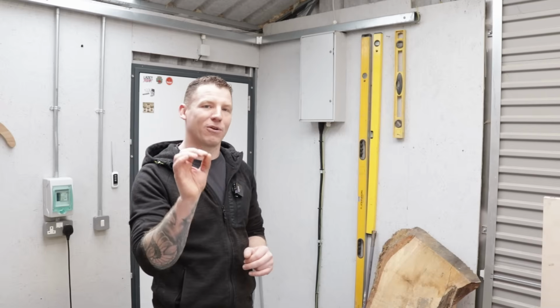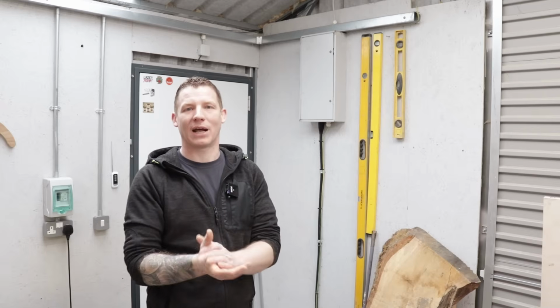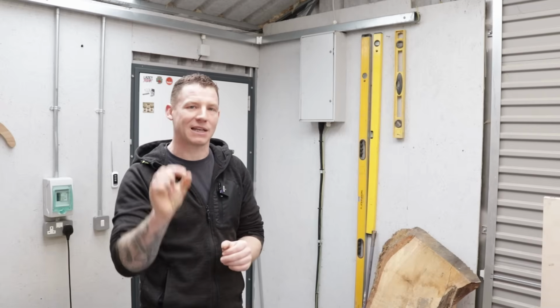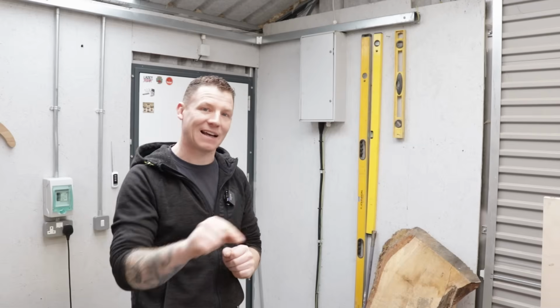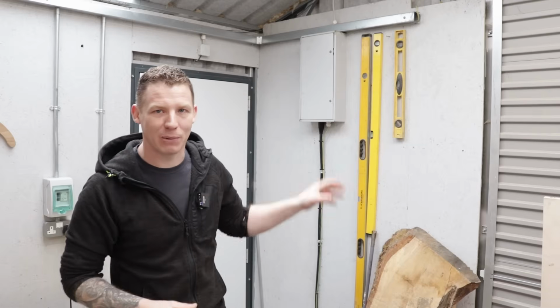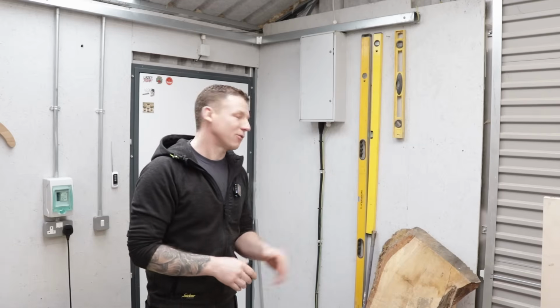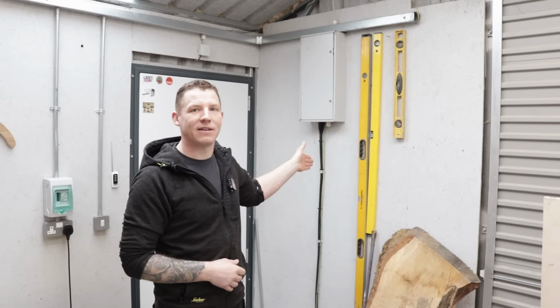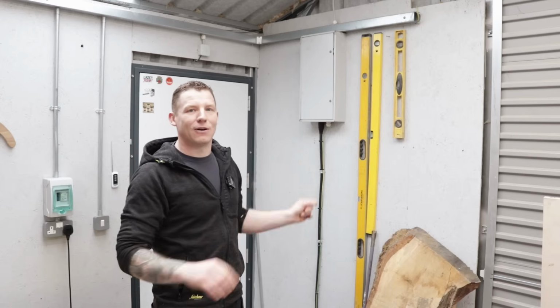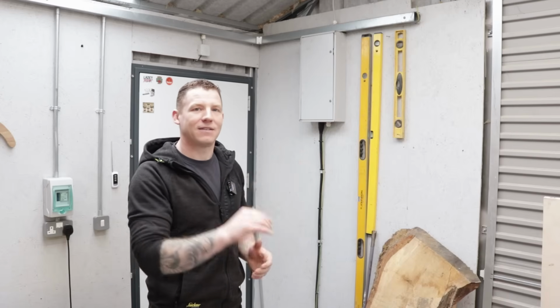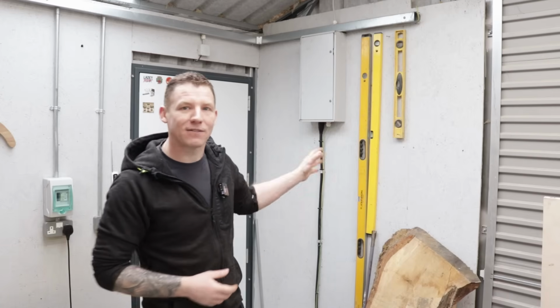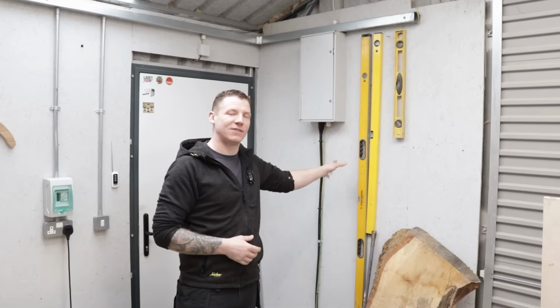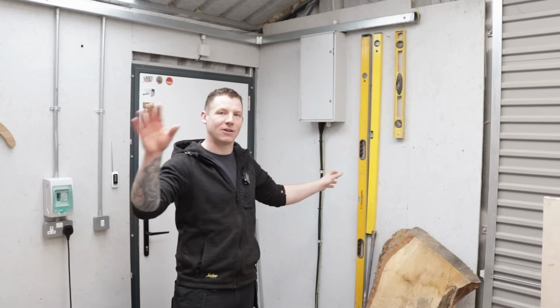And there's another important factor for that, which is what's known as the fault loop impedance. We want to keep that as low as possible. I'll get into that as this video goes on. I'll explain a bit more what that is. But my first advice, the very first point, is size your mains cable to your load and to the distance and to future expansion. So ask your electrician to oversize this cable.